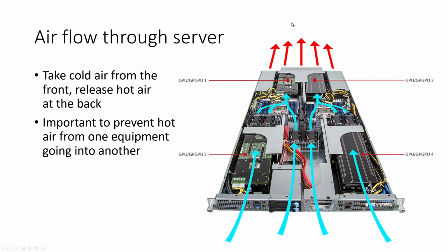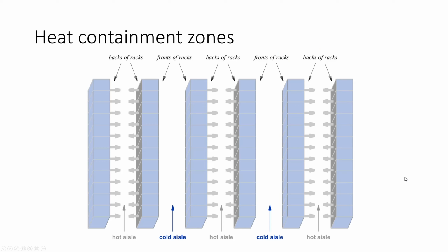It's very important that hot air coming from one server or one switch doesn't get into another piece of equipment, because otherwise you're going to have hot air going inside an equipment, and then that equipment might get very hot and malfunction. So operators build heat containment zones in data centers.